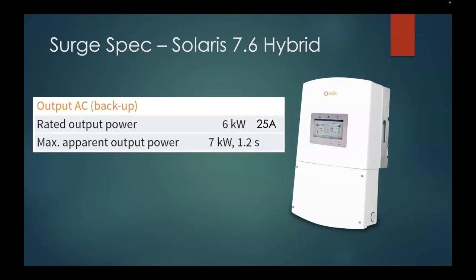We'll just put that in as 25 amps. I put that current in there because when you look at the nameplates of big compressors and motors, they give their startup spec in current. This inverter's surge power, which they call maximum apparent power, is 7,000 watts for 1.2 seconds. That's 29 amps.